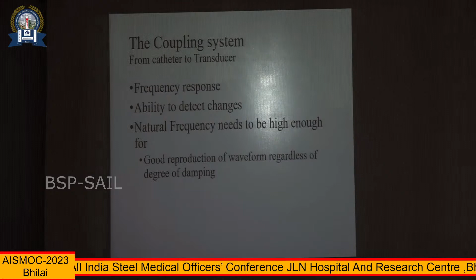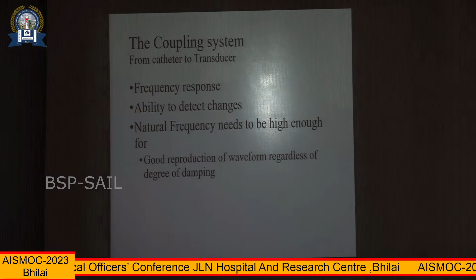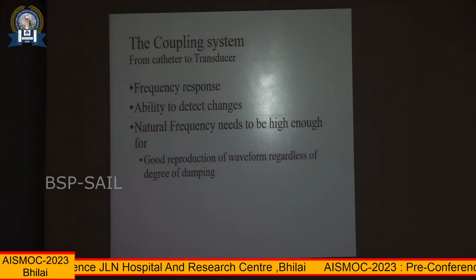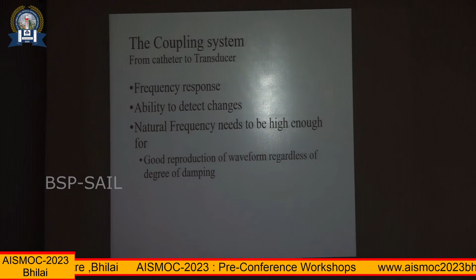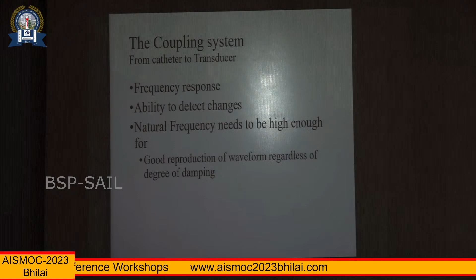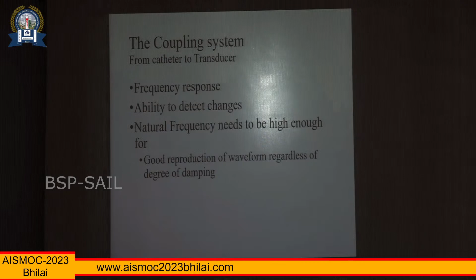Okay. And you have to test whether the transducer is functioning adequately or not, because over a period of time the transducer may lose its accuracy, and by doing the fast flush test you have to always keep a check whether the transducer is optimally showing the readings. Because a little bit of error here and there may not have a big impact on arterial blood pressure tracings, but for CVP or pressures where you have lower pressures, a little bit of change in the transducer function may give erroneous values. So when we test the system, we call it frequency testing or checking of the frequency response.